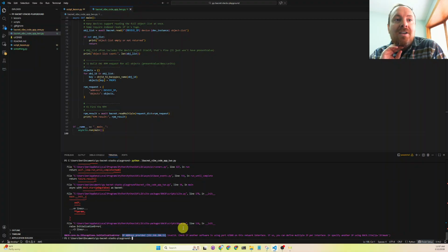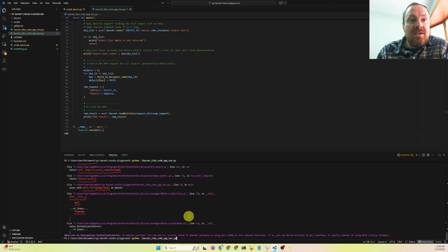So that's why the operating system tells you that only one BACnet application on the computer can listen to this socket, UDP port 47808, which is default for BACnet. And it's different from outbound TCP protocols like HTTP requests or MQTT, where you could have dozens or hundreds of outbound request-based protocols running at the same time, but BACnet is unique and we can only do one.